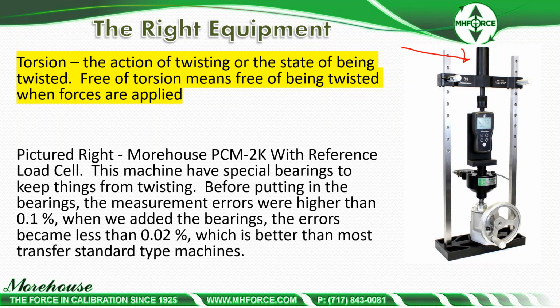Morehouse, what you're seeing is a PCM 2K with reference load cell. This machine has special bearings to keep things from twisting. Before putting in the bearings, the measurement errors were higher than 0.1%. We added the bearings, the errors became less than 0.02%, which is better than most transfer type machines.